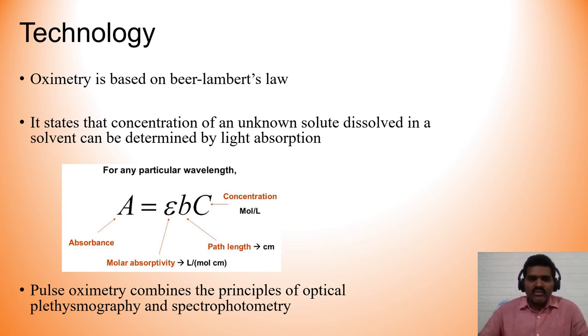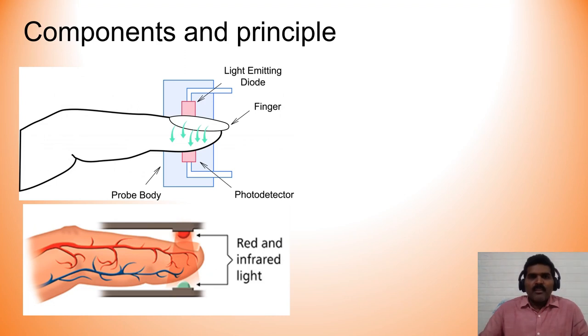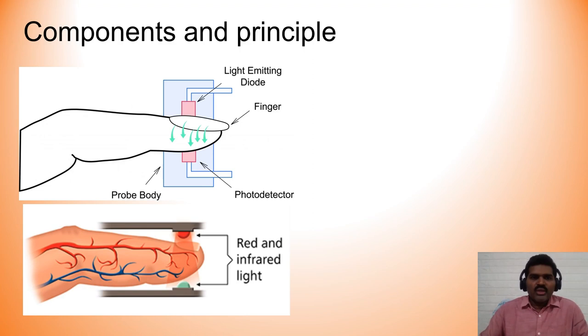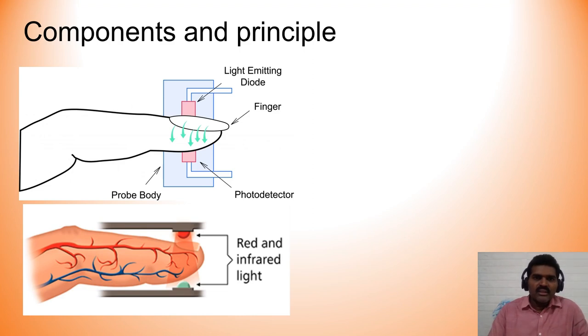Pulse oximetry combines the principles of optical plethysmography and spectrophotometry. The basic design described here is the finger-mounted pulse oximeter, though other types can be mounted on the earlobe, nose, or nasal septum to monitor central oxygen. The most commonly used is the finger-mounted pulse oximeter. On one side of the probe you find a light-emitting diode.